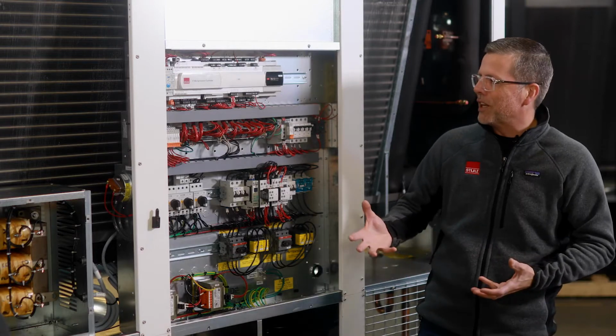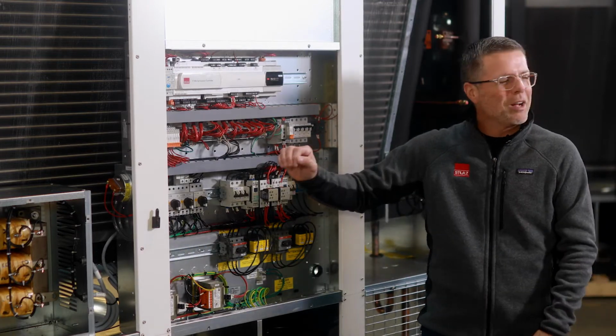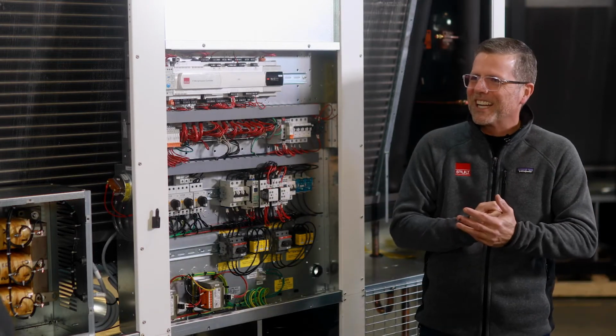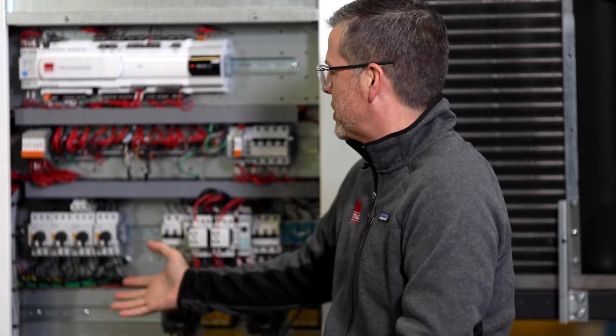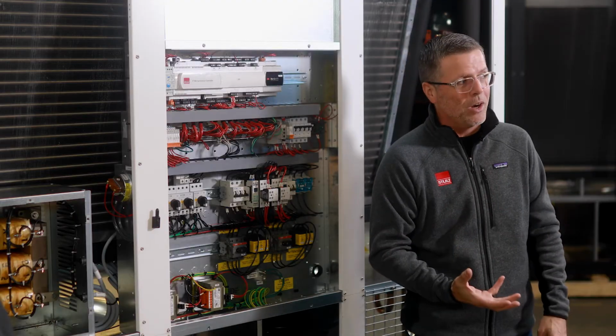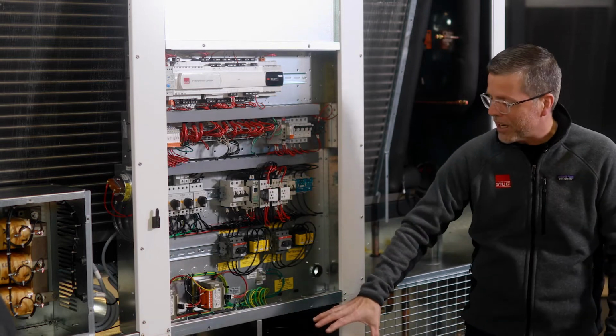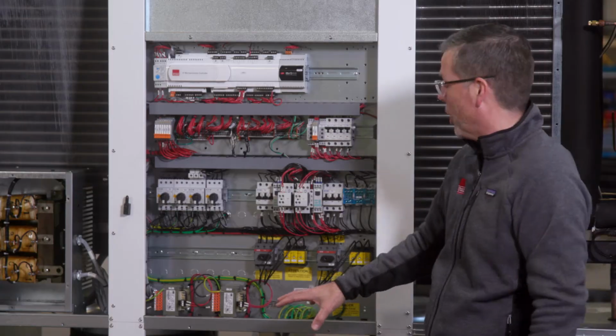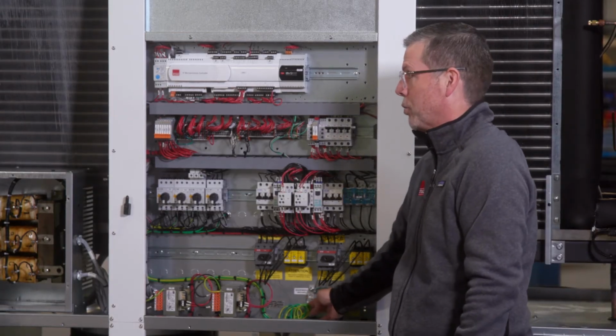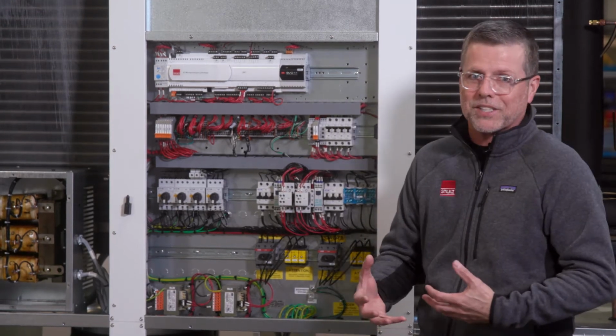So it isn't one of those things where we're gonna pull every single wire laser tight with 23,000 wire ties. The service personnel are gonna need to get to these units. These are 3-phase products. They're gonna need to get accurate voltage across all 3 phases. They're gonna need to get accurate amp draws as well. So you'll see service loops throughout when we do our builds. You'll see service loops on the ground wiring as well. We wanna make sure that we're not getting any feedbacks to ground.